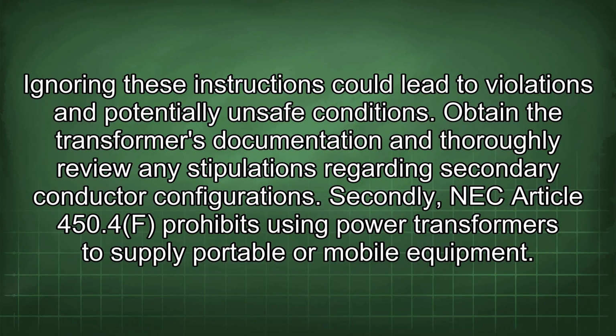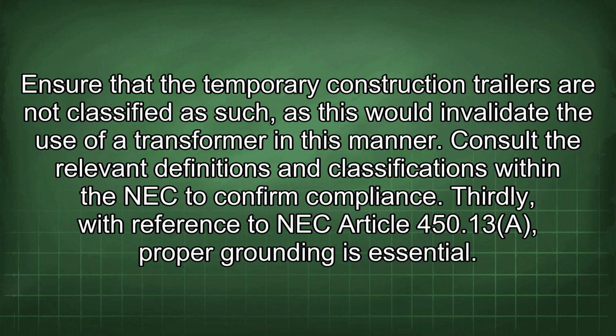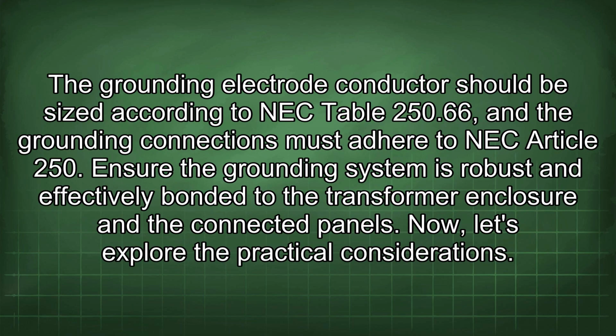Secondly, NEC Article 450.4f prohibits using power transformers to supply portable or mobile equipment. Ensure that the temporary construction trailers are not classified as such, as this would invalidate the use of a transformer in this manner. Consult the relevant definitions and classifications within the NEC to confirm compliance. Thirdly, with reference to NEC Article 450.13a, proper grounding is essential. The grounding electrode conductor should be sized according to NEC Table 250.66, and the grounding connections must adhere to NEC Article 250. Ensure the grounding system is robust and effectively bonded to the transformer enclosure and the connected panels.